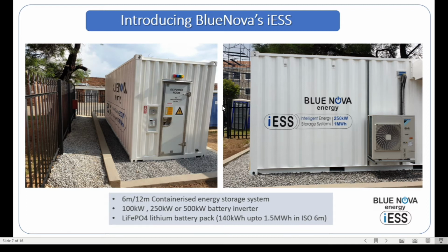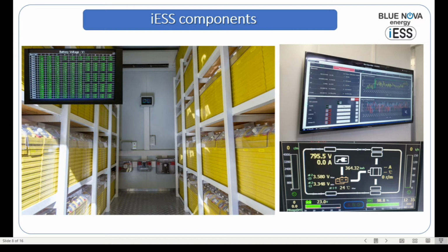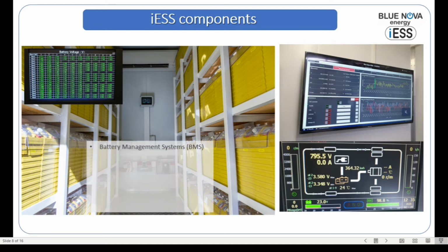Looking a little bit more into the details of the system, we have an integrated battery management system, which is responsible for maintaining safety and health checks on all the systems and allows the system to protect itself if there are any unwanted conditions. There's an energy management system which manages the charge and discharge of the battery, and also allows energy optimization between the grid, the solar components, the diesel components, and other energy sources. The system comes with an integrated remote monitoring and management system, which allows complete off-site monitoring. We're running a 24/7 remote monitoring system that monitors all the alarm and warning conditions and allows essentially a preventative maintenance strategy, while the consumer doesn't really have to worry about these items.